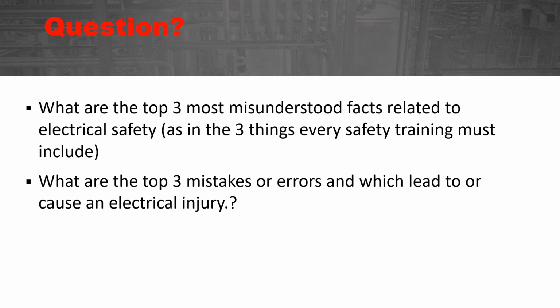One thing that I've also seen is the failure to recognize all known voltage sources or all known power sources. So someone will go into a panel and just disconnect the main disconnect switch or the main breaker and say, okay, everything else downstream in this panel is de-energized. A, the incoming conductors are not de-energized, and B, there could be another known source or a source that's unknown, such as a capacitor or a secondary feed of power into that panel that back feeds into where they're working. And they'll just isolate that one breaker, and then they'll go in and do their live work, and they'll get shocked or electrocuted because of their failure to recognize all known or all available power sources.